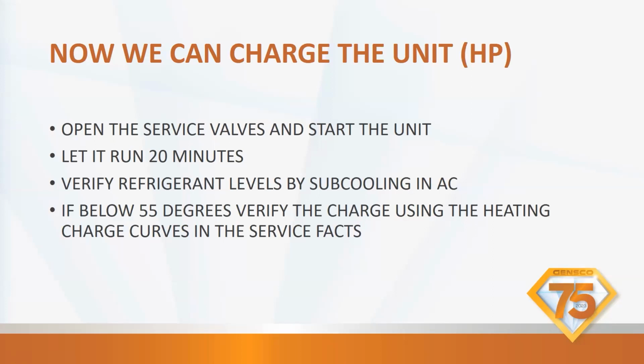Basically what it is talking about is subcooling and superheat. For subcooling, the refrigerant comes out of the compressor into the condenser. It's 100% vapor when it goes into the condenser. As the fan blows across the coil, it cools down the refrigerant and turns it to a liquid. As it turns to a liquid, it takes the saturated temperature, which is liquid and gas together. Once it gets down to 100% liquid, it starts picking up subcooling. So anything below the saturated temperature is subcooling.